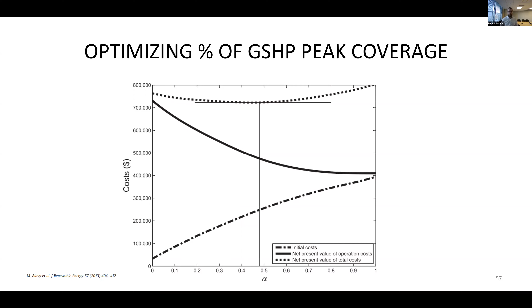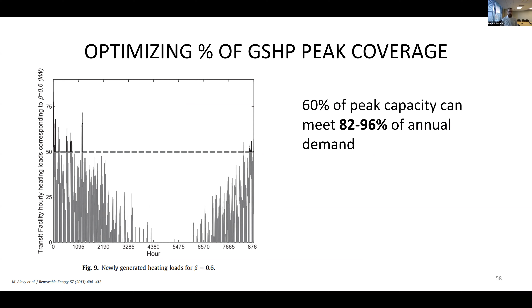This formula tells us exactly what percentage of heating load we should be sizing for. In this scenario, they found that a 60% peak capacity could meet 82 to 96% of the annual demand. By using this optimization technique, they found they could reduce their payback period up to 12 years over a conventional system. And if you were to use just a ground source heat pump, this would be a 19-year payback—pretty close to end of equipment life.